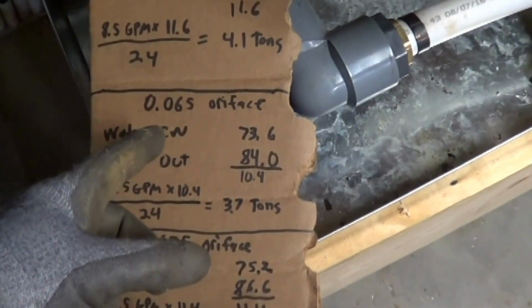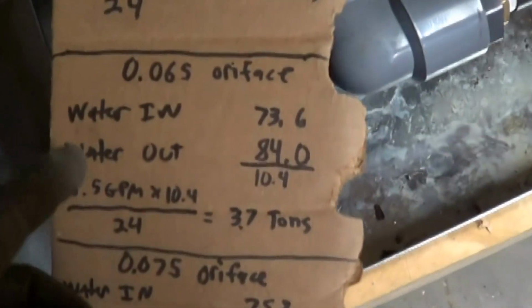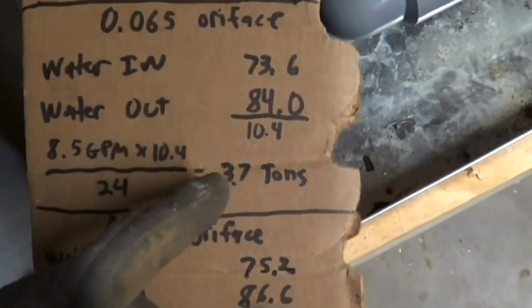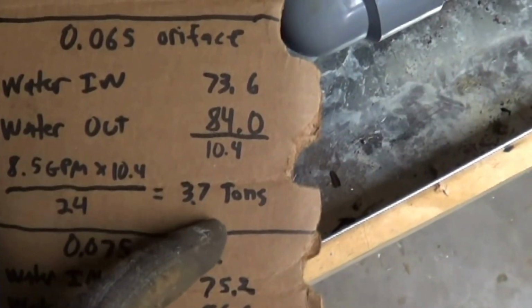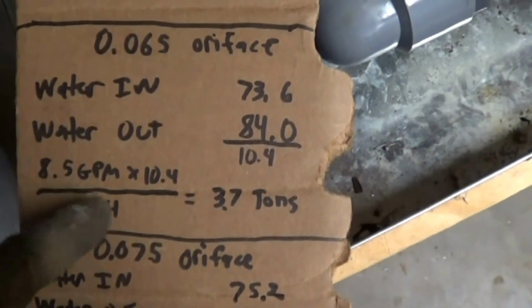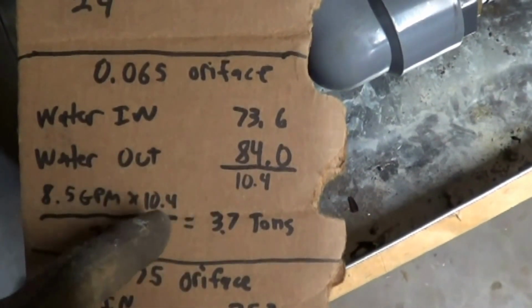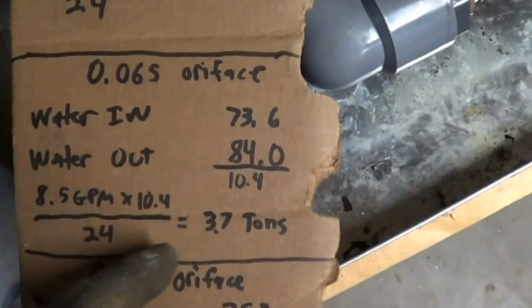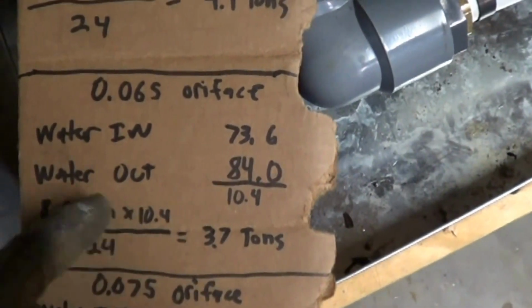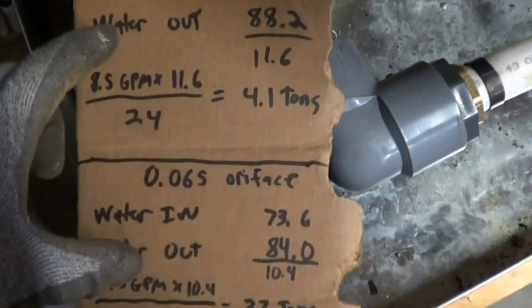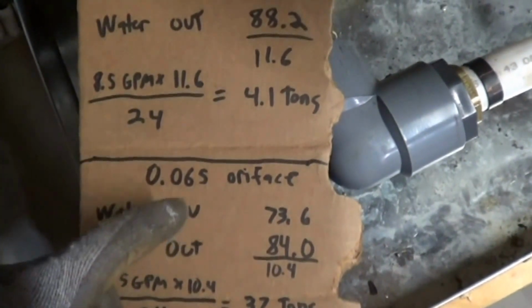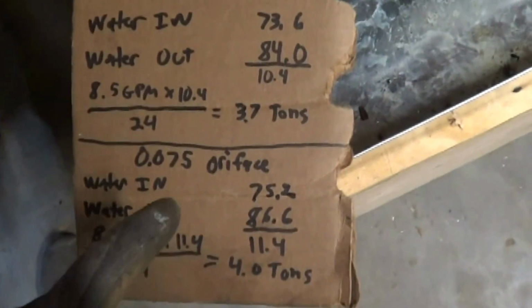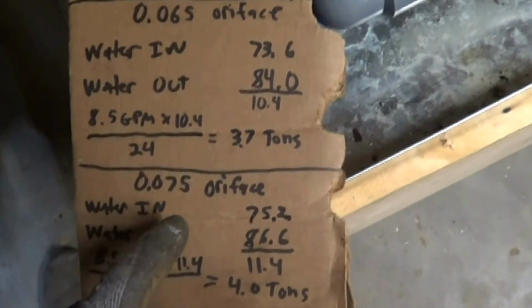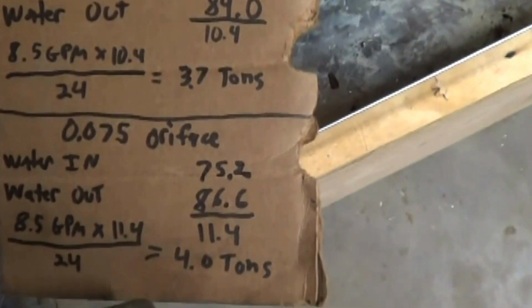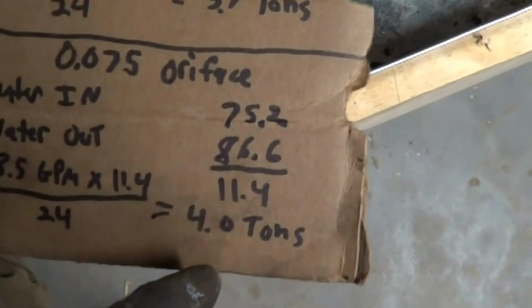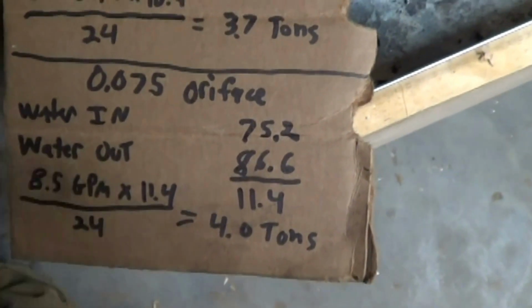And then I went to the original orifice, which is 65 thousandths, and then you do the numbers, and as I saw, the tonnage was lower because I got my 8.5 gallons per minute times your temperature delta across your water coil, divided by 24, 3.7 tons. So I knew I needed more feeding because the smaller orifice was pinching it off too much. So I drilled it out to 0.075, and my numbers got better. And so you can see I'm getting 4 tons with that size orifice.